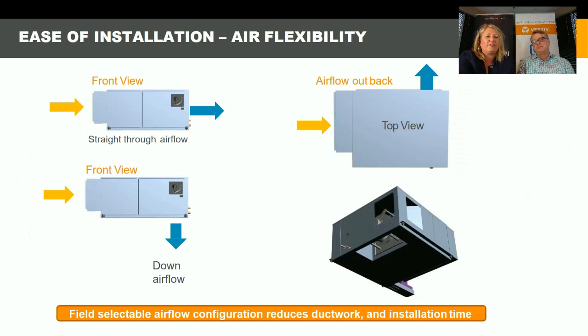It's available in several configurations for easy installation. So you have an easy way to install it depending on your space. You can hang it in the space or outside of the space and duct it over to the room. So if the customer wants to hang it outside of the closet to avoid any dripping or anything like that, they hang it outside and then duct the cooling and just blow it right down onto that IT load.